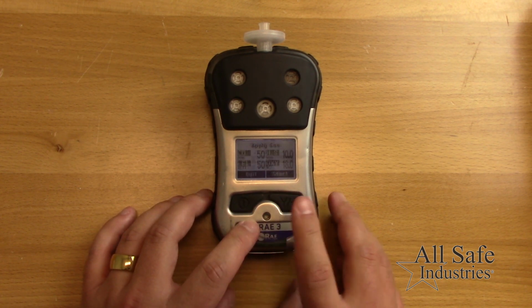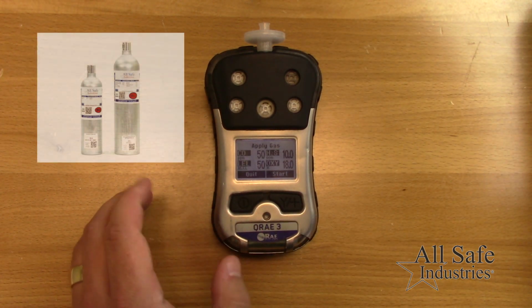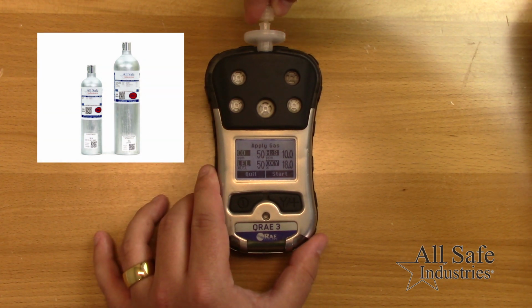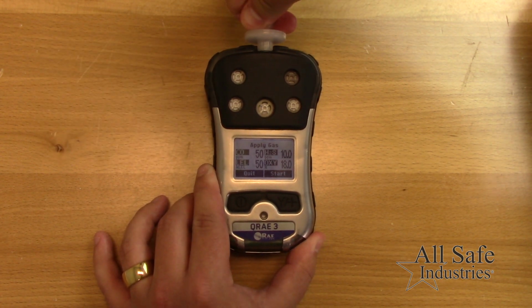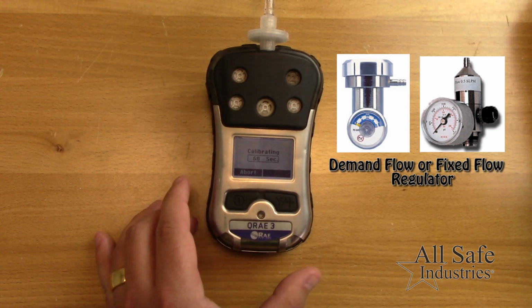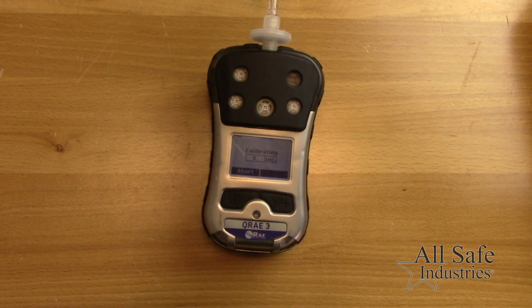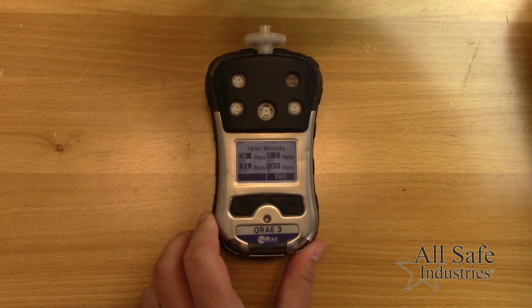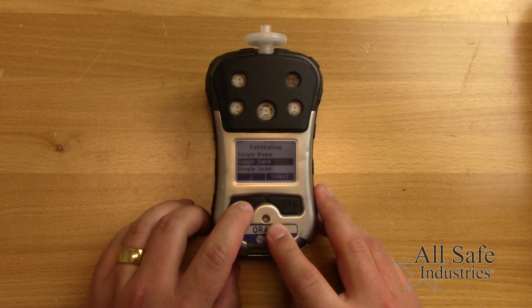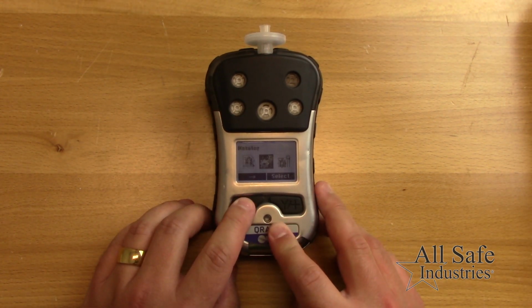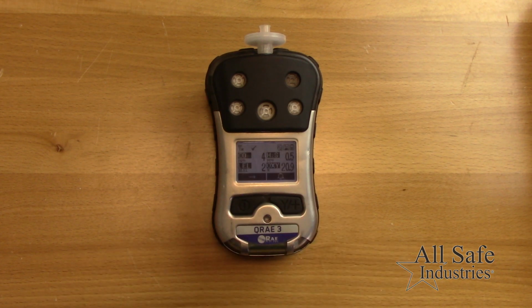The display will show the concentrations of gas that the meter expects to see. Ensure your cal cylinder values match and connect the gas flow to the inlet of the meter. At the end, the screen will display the values and either a pass or fail for each sensor. Remove the gas, and if all sensors passed, use the exit menus to return to normal operation mode.